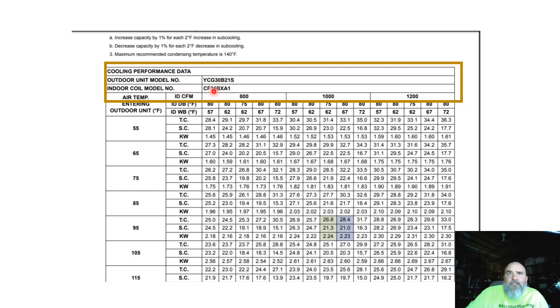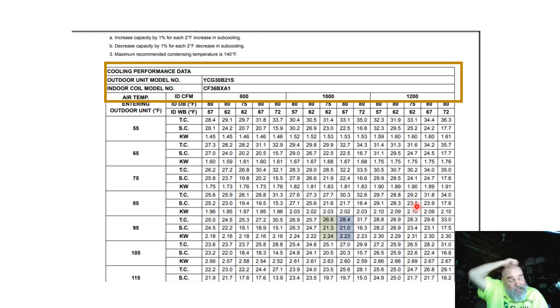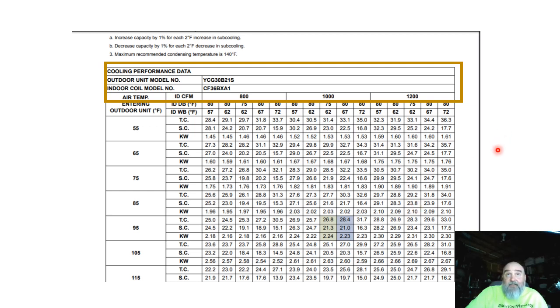This is a 036 indoor coil paired with an 030 outdoor section. I don't care if it says 036 — in my mind that is a two-and-a-half ton coil, because look at the actual capacity numbers at our 67°F/75°F/62°F conditions. Those are the numbers I'm supposed to be using. It's nominally a two-and-a-half ton air conditioner and it doesn't even make two and a half tons at our interpolated capacity. I think I'm exceeding 500 CFM per ton with this selection, and I like it.